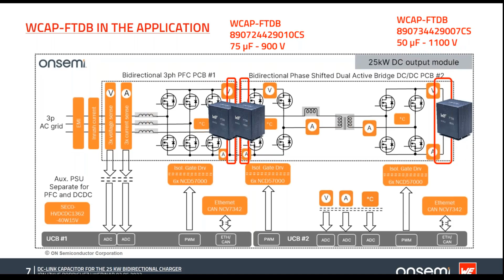Of course, DC link only refers to the placement of the capacitors. In theory we could use any type of capacitor here, but with the amount of power handled by this application, we can only consider either film capacitors or aluminum electrolytic capacitors. Both technologies are valid, and each case must be carefully considered because there are advantages and disadvantages. So it's a complicated comparison.